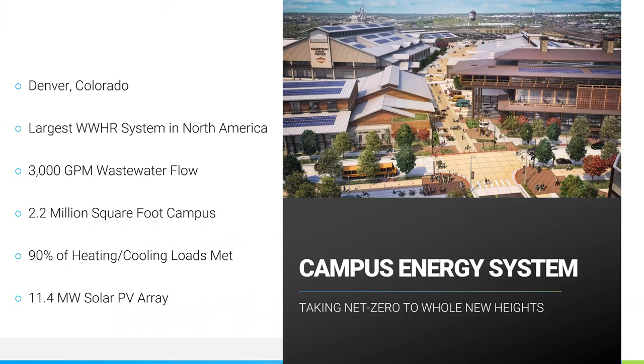Another project in Denver will be the largest wastewater heat recovery system in North America, providing about 3,000 GPM total of wastewater flow. The total campus area is about 2.2 million square feet. And just from the wastewater flowing beneath it, about 90% of all heating, cooling, and hot water loads will be met. And that was just using a very small percentage of the wastewater flow. So you could get the sense that they're really just dipping their toes in the water to see how effective this could be. But then, as you can see there on the rooftops, there's about 11.4 megawatts total of solar PV array around the entire campus as well.